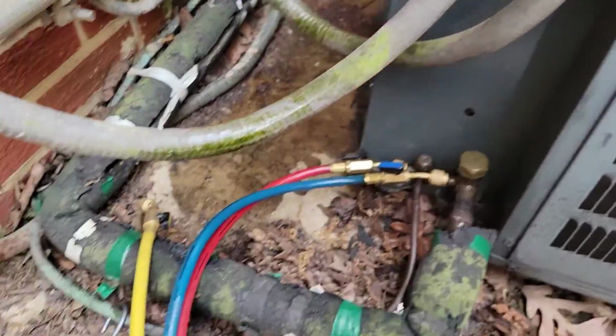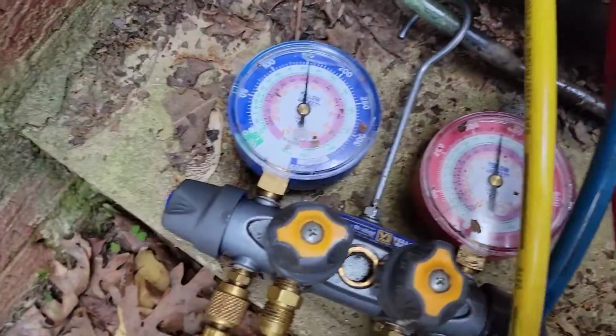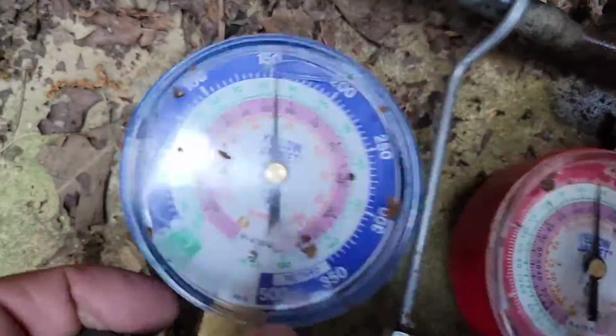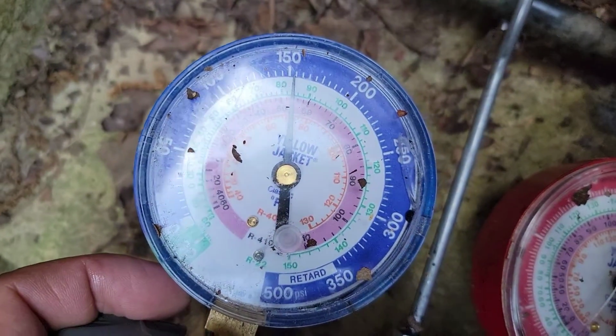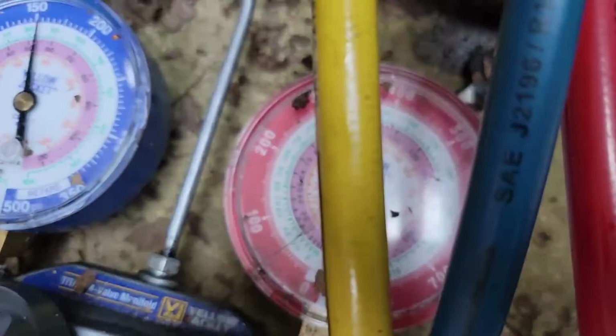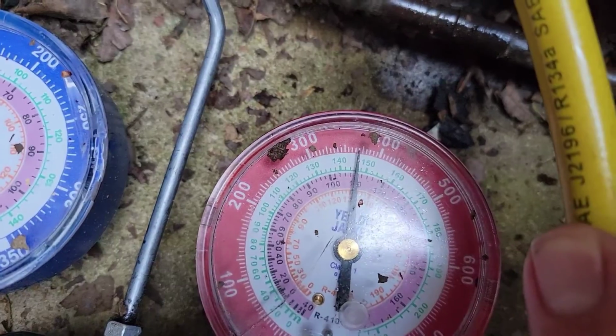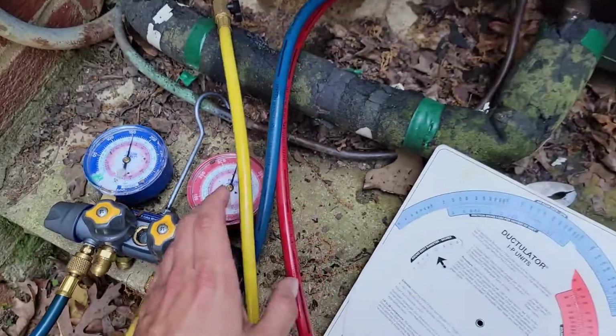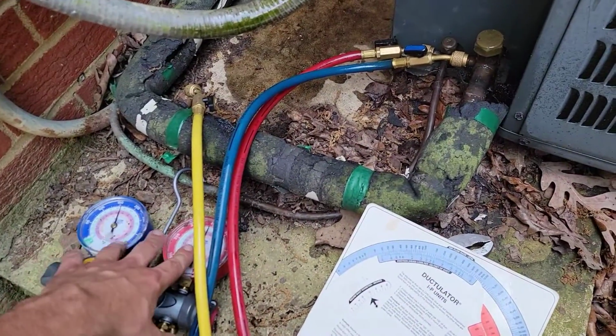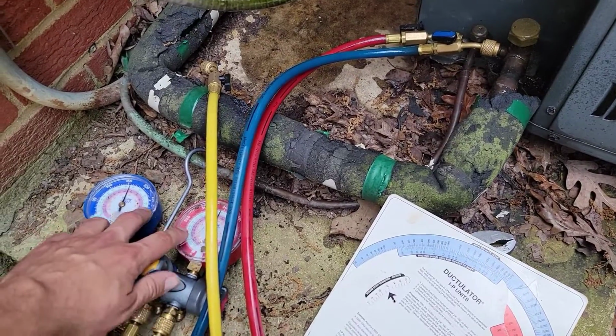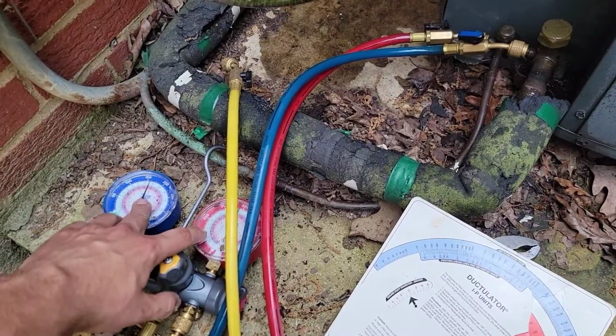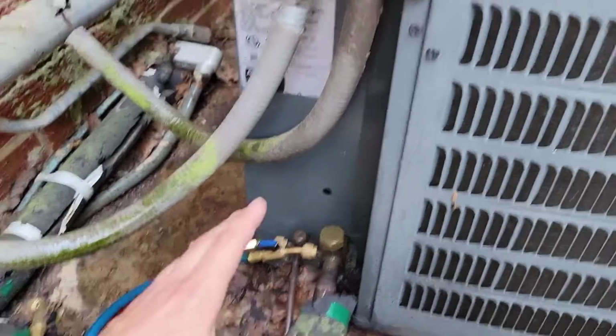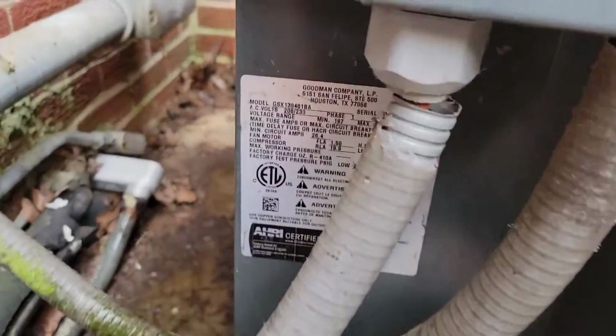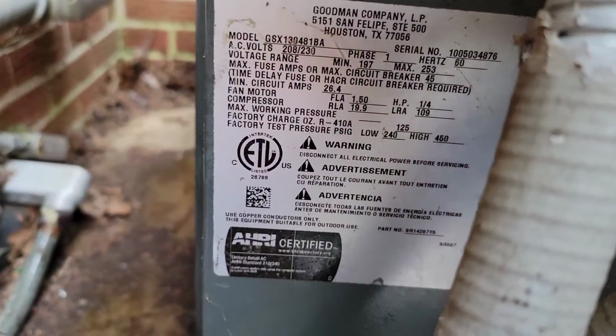We're outside at the unit. This is the outdoor section and we've got 155 on the suction and we've got 375 on the head. Now, I actually got a recovery tank and recovered about a pound out of this because I thought it's overcharged. Obviously, it's overcharged. It's about 85 degrees outside.